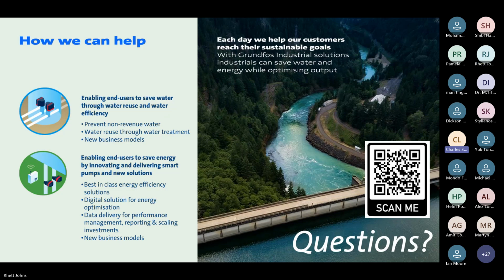And those integrated VSDs, I've actually come across this a few times myself, and that again, in addition to obviously reducing your pump size, something that we talk about a lot at Grundfos is reducing system complexity. And that's where the integrated VSDs can be connected directly to your sensors. So you wouldn't necessarily, in some cases, need to have external control panels or everything like that. That control can all be consolidated into the VSD itself. So you not only, as Rhett was saying, downgrade the size of the pump, but you also might be able to reduce your system complexity, which we see quite a lot of.